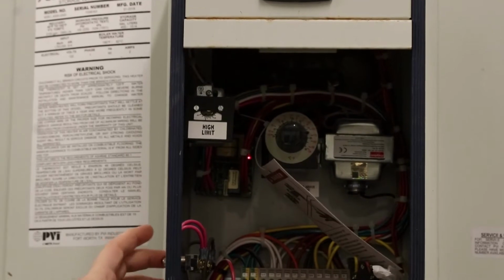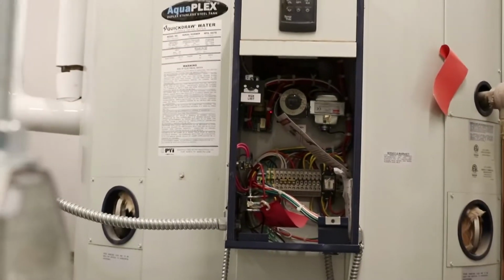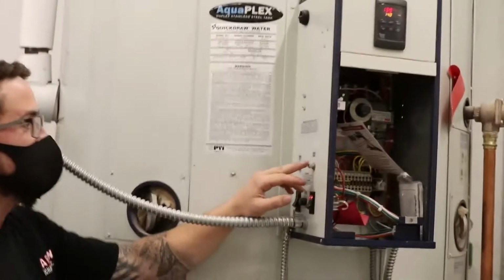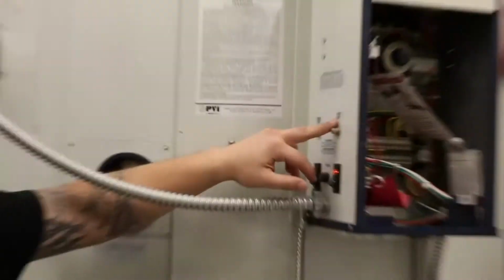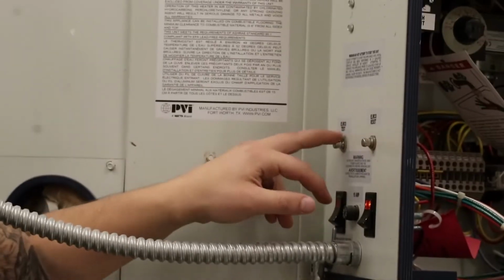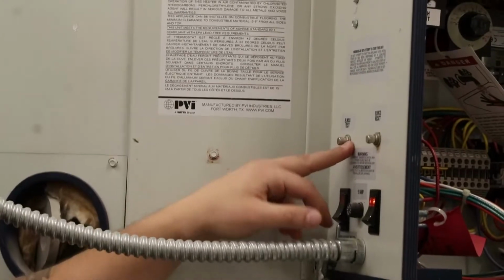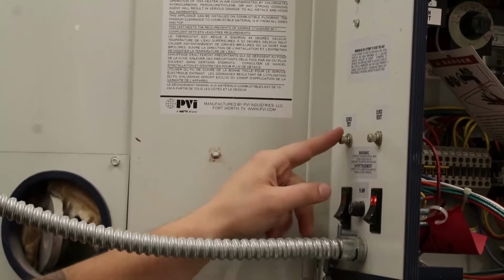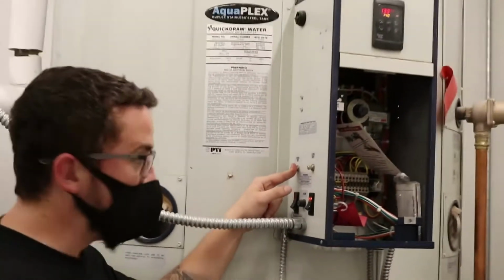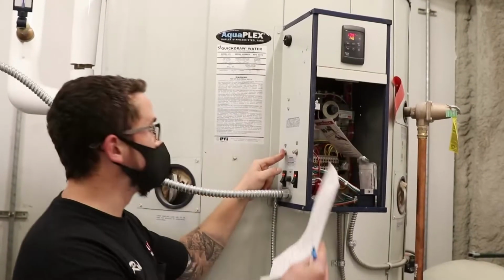I'm going to show you how to test it. There's two buttons on the side. One is ELWCO, that's electronic low water cutoff reset. The other is electronic low water cutoff test. If I want to test the function of this control, I will hold that button down. While holding it down, keep an eye on the circuit board in the panel. I'll silence the alarm here.